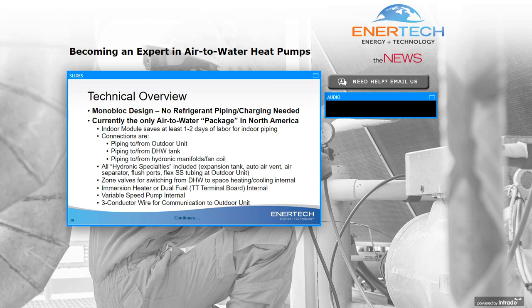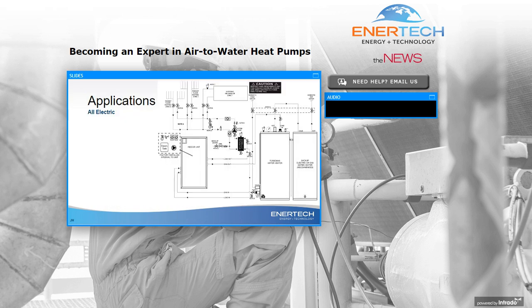I mentioned earlier, we can choose a dual fuel if we have a boiler backup, or there's a 9kW immersion heater that's available for an all-electric system. The pump is variable speed inside that module. It's a Grundfos UPMXL, very efficient, and will change based upon delta T control. And to make things easier, we don't have a whole lot of wiring between the two units. It's just a three-conductor wire to communicate between the indoor and the outdoor sections. Applications become a lot easier when we have all that packaged.